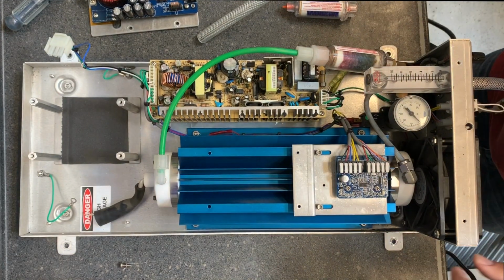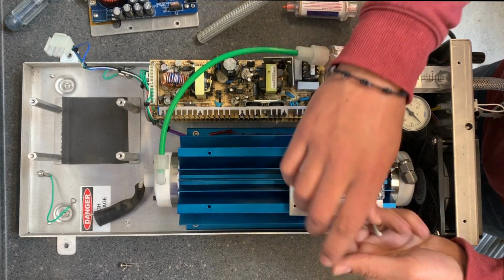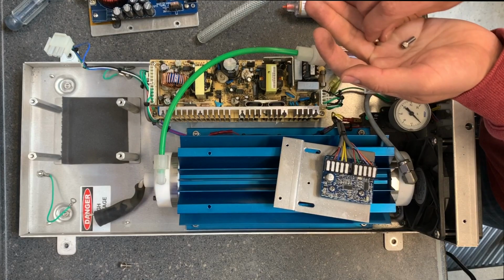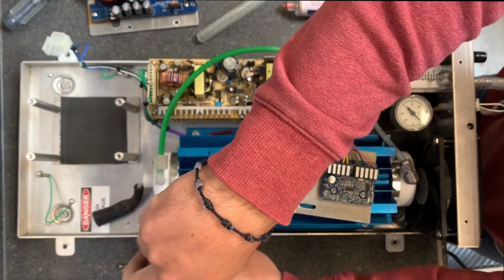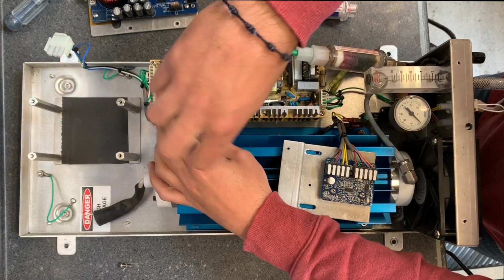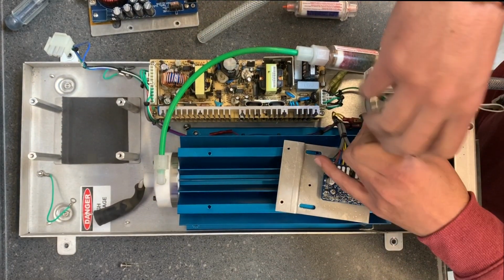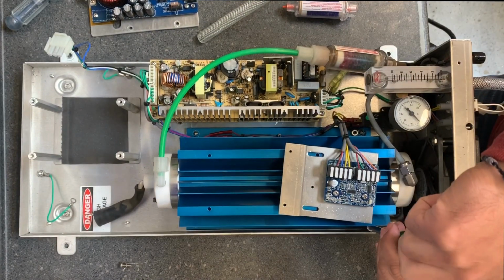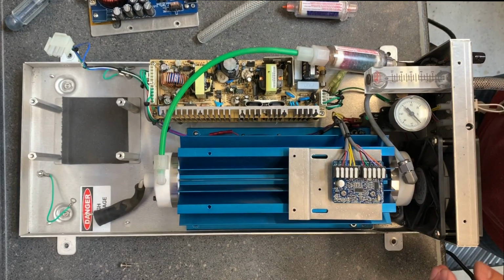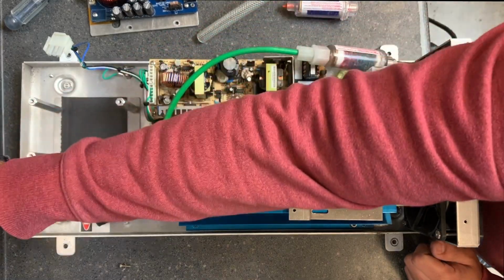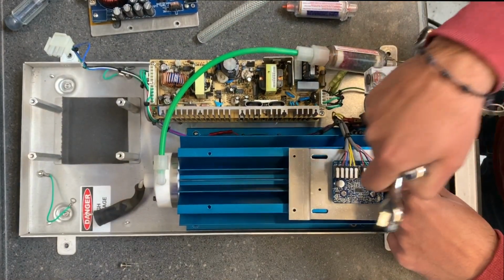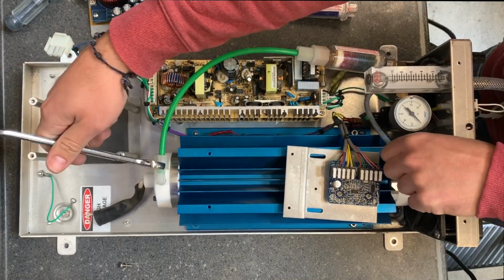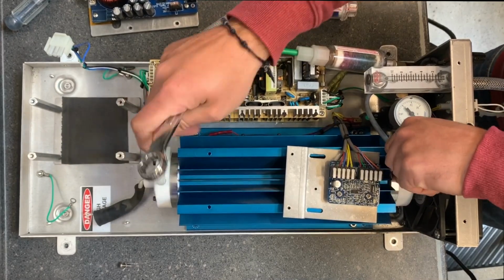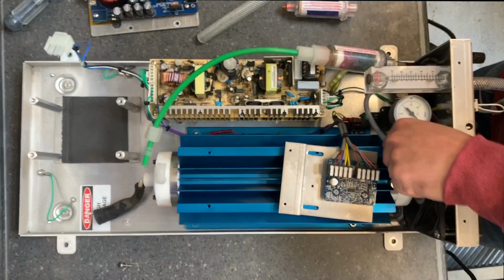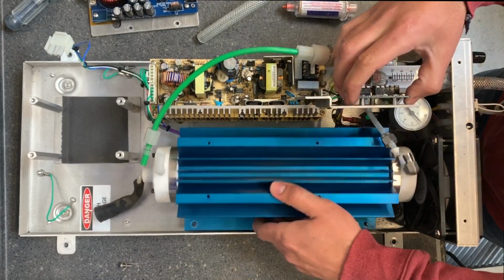So you want to unmount the unit. You want to unmount this plate that's holding the 4-20 milliamp board to the chassis. You want to undo the 4 screws holding it down. Make sure you don't lose those nuts, as you do want to properly ground the chamber once you're done. And you want to disconnect the lines, which you're going to need a 5/8 and a 9/16 wrench. 9/16 for the stainless steel side, and 5/8 for this side, for the Kynar. So once the line's disconnected, you go ahead and pull it out. The chamber should come out.